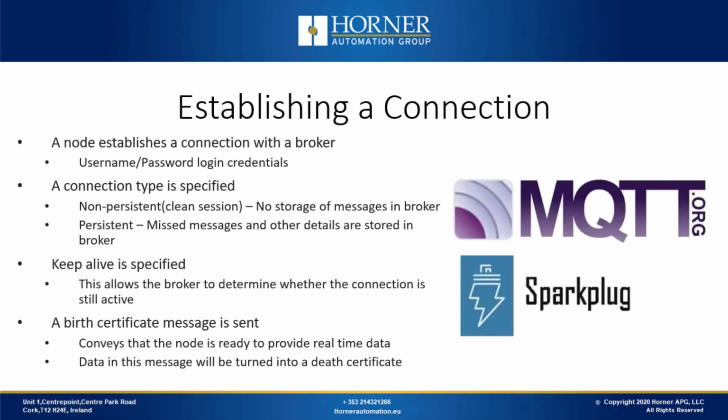In a not clean session, there is a persistent connection, meaning all missed messages are stored in the broker. Another thing you must specify when establishing a connection is a keep alive. A keep alive is a period of time in seconds where you're going to ensure that the node is communicating with the broker, so that the broker knows that the node is healthy. So if you, for example, set the keep alive to 30 seconds, it would check every 30 seconds to make sure that it's still communicating with the broker. And if the timer expires, it's going to inform any subscribers that are interested in said data that it is stale or that the connection is lost.